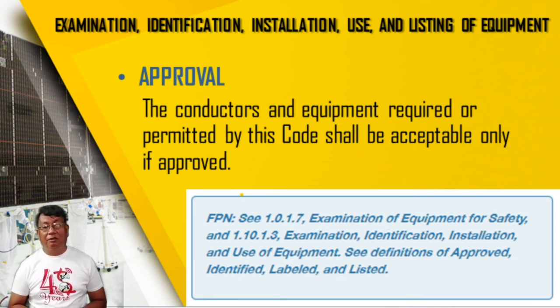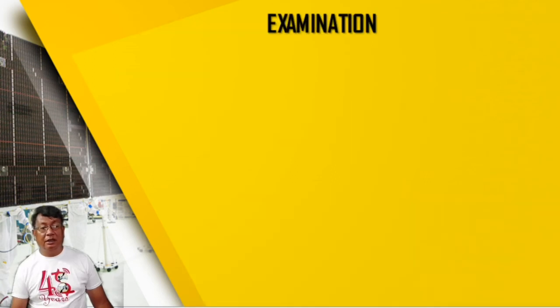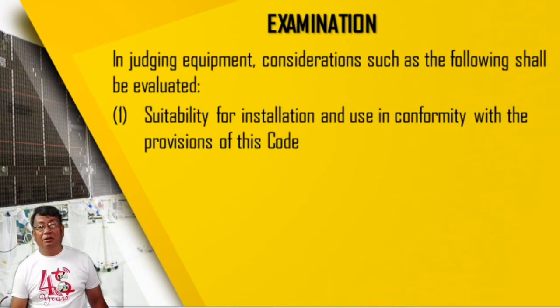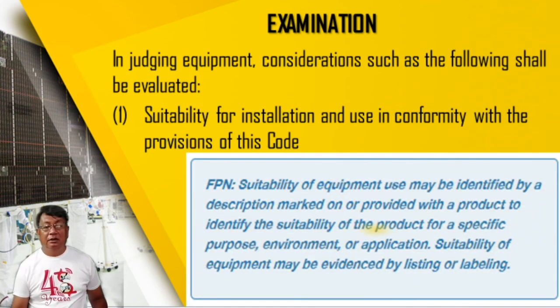It's very clear. So according to the fine print notes 110.7, examination of equipment for safety, and 110.13, examination, identification, installation, and use of equipment. See the definitions of approved, identified, labeled, and listed. So these are the fine print notes. Okay, we have 110.7 and 110.13. So for examination, in judging equipment, considerations such as the following shall be evaluated. Okay, suitability for installation and use in conformity with the provisions of this code. Suitability, no, so that's very clear. And then we have here suitability of equipment used may be identified by a description marked on or provided with a product to identify the suitability of the product for a specific purpose.